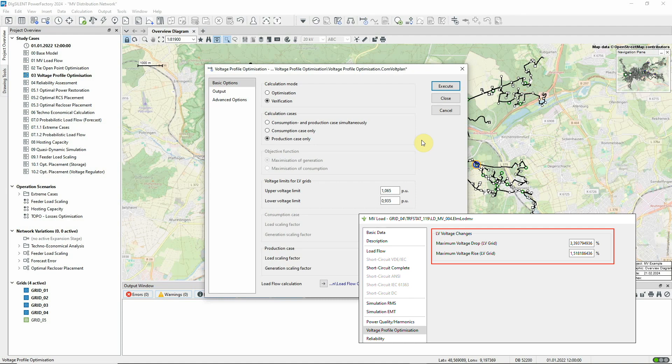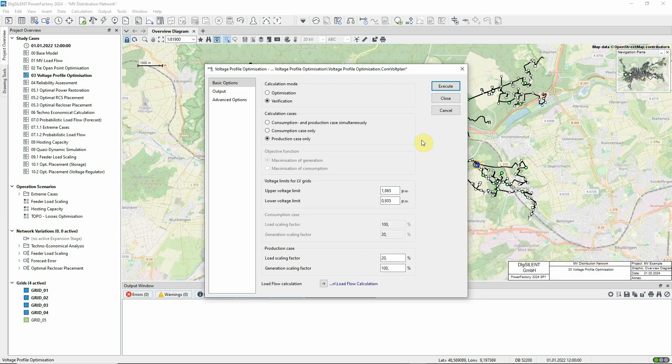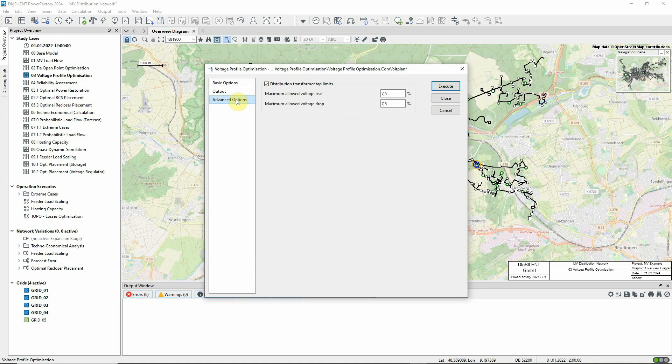When the calculation is executed, the resultant per-unit voltages in the LV grids are then compared with these limits. Here, we can see the scaling factors to be used for the analysis. And here, we also define limits for the voltage rise or drop across the transformers.